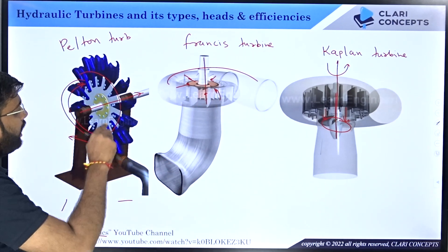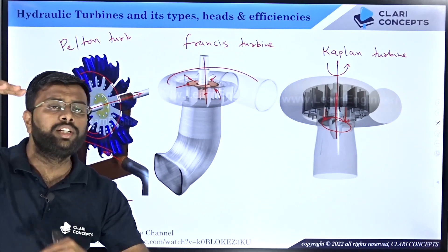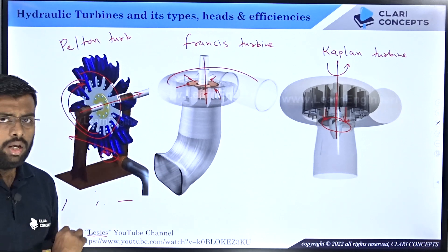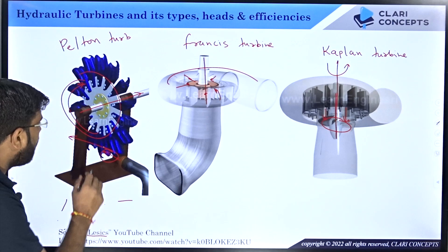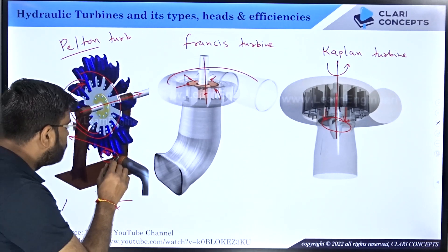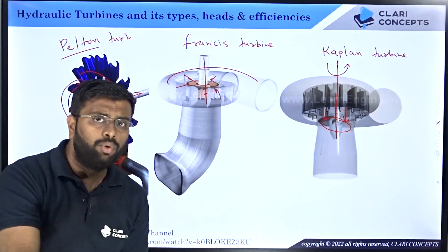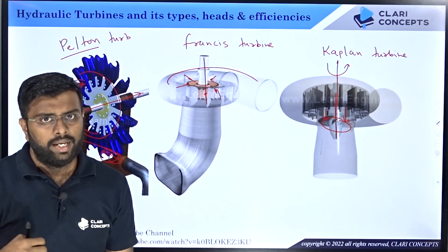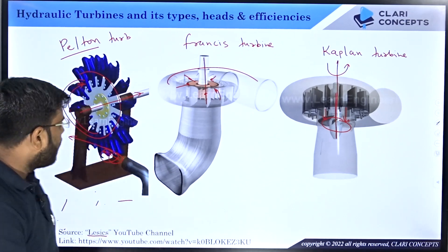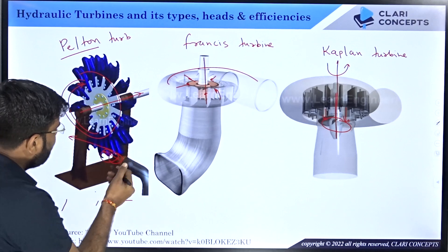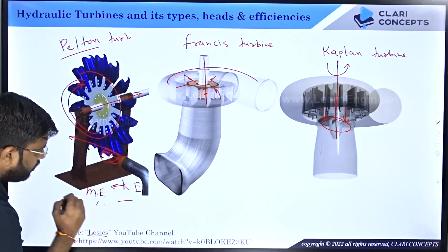The Pelton turbine is majorly used for very high head, because as head increases velocity increases, and as velocity increases the kinetic energy increases. In the Pelton turbine, the energy available in the water at the runner is purely kinetic energy, and that kinetic energy is absorbed and converted into mechanical energy of the shaft. When water flows in a pipe, it has two energies: kinetic and pressure. The Pelton turbine uses only kinetic energy to produce mechanical shaft energy.